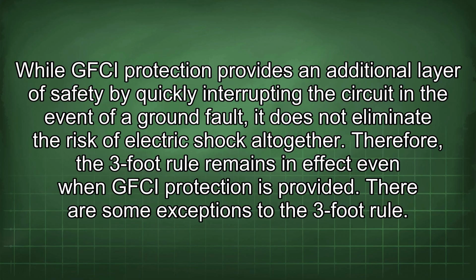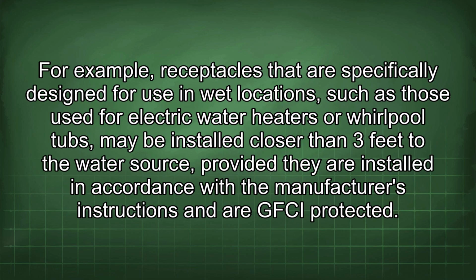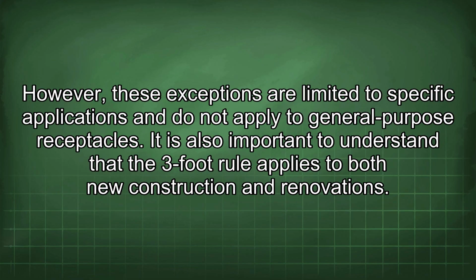There are some exceptions to the 3-foot rule. For example, receptacles that are specifically designed for use in wet locations, such as those used for electric water heaters or whirlpool tubs, may be installed closer than 3 feet to the water source, provided they are installed in accordance with the manufacturer's instructions and are GFCI protected. However, these exceptions are limited to specific applications and do not apply to general-purpose receptacles.